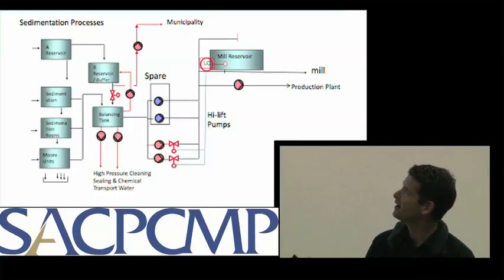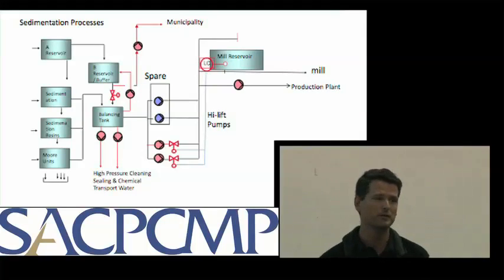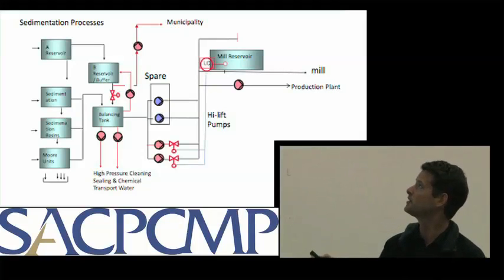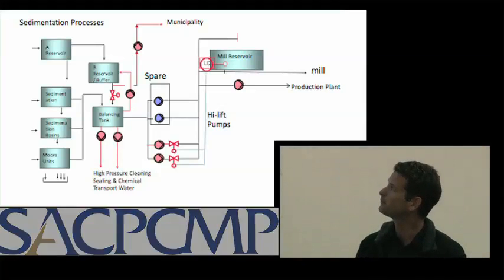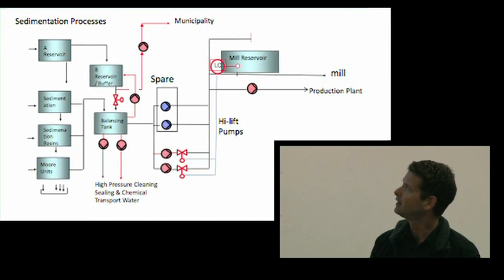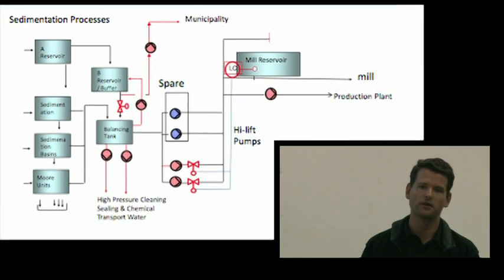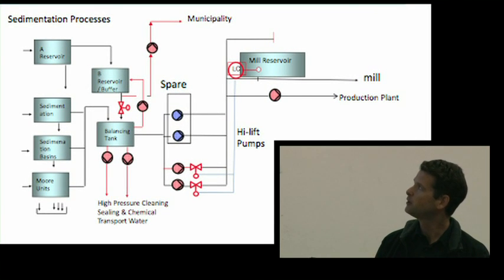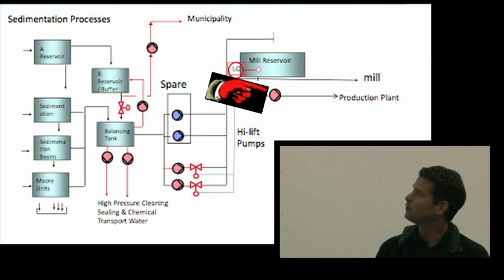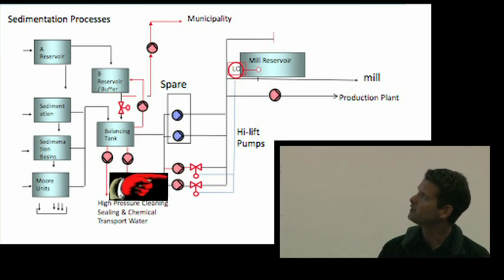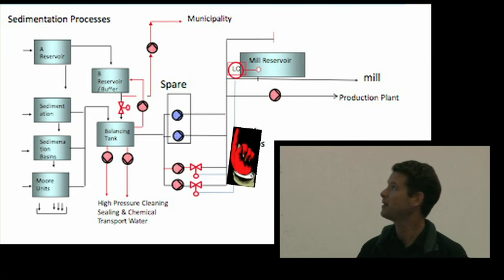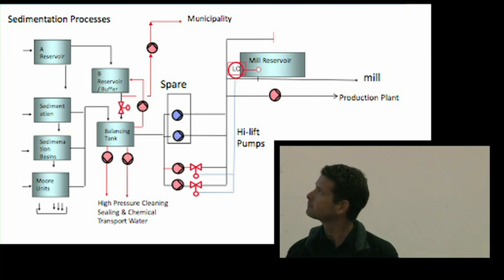Then there was this issue that I mentioned right at the end. Just before we implemented the project, someone said to me, oh, but there's another production plant drawing off the main mill reservoir. So what do we do about that? The idea was, first of all, that they were struggling with their supply pressure, so I put in a very small booster pump to boost their supply pressure. It's literally a 2.2 kilowatt pump. But when we stopped pumping here, I modified the piping system so that we siphoned back off the mill reservoir to supply them, as opposed to pumping to them.